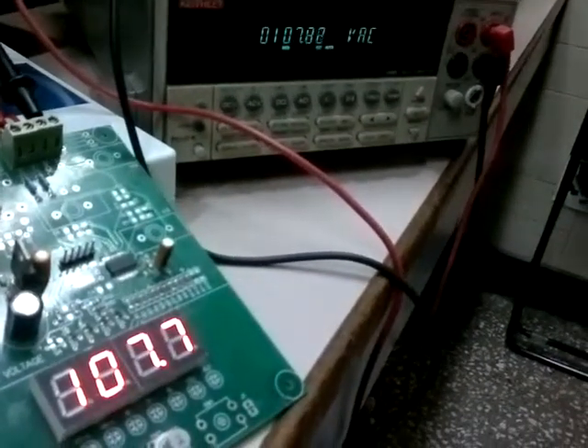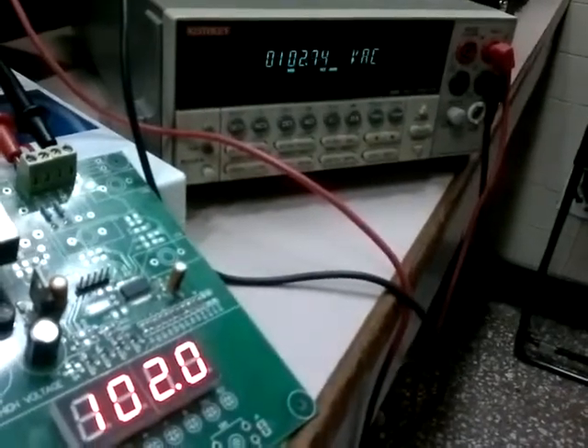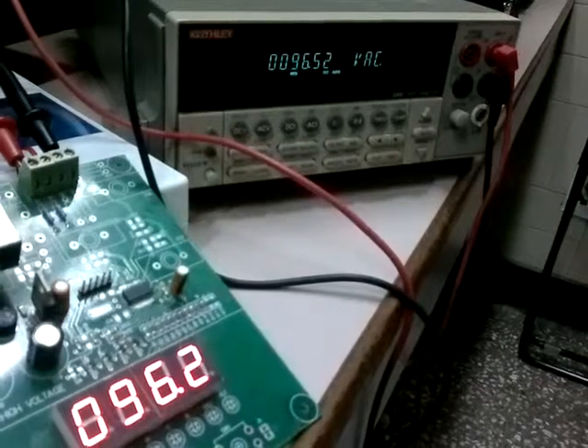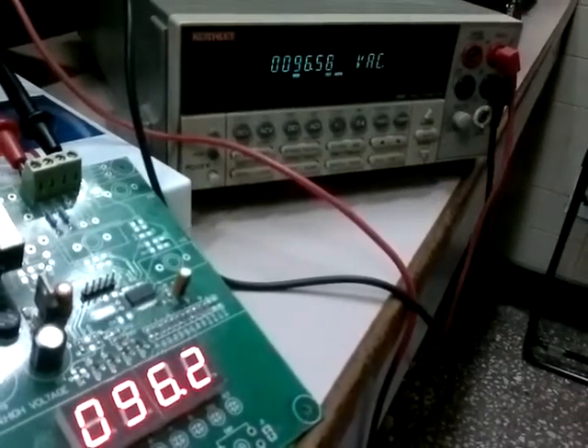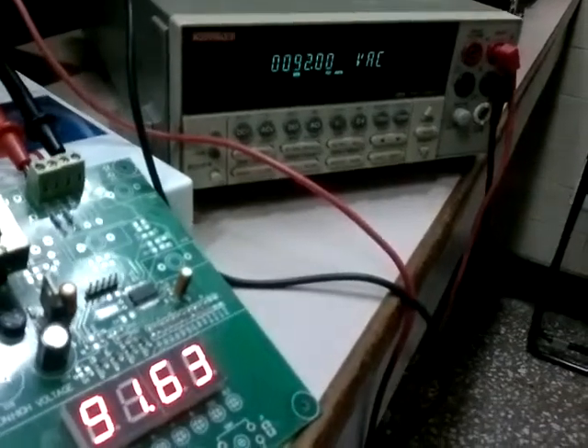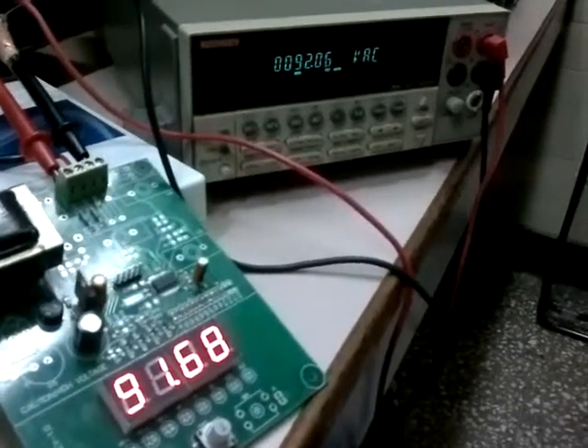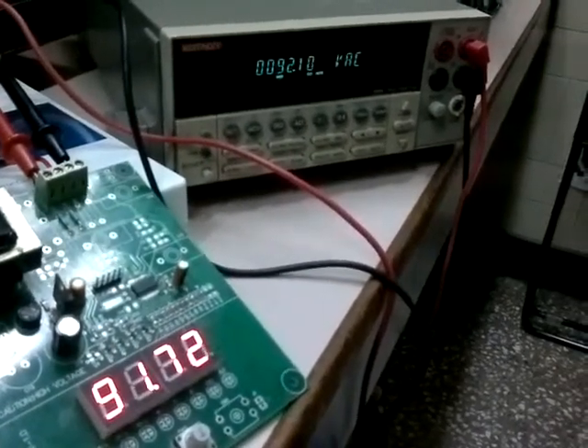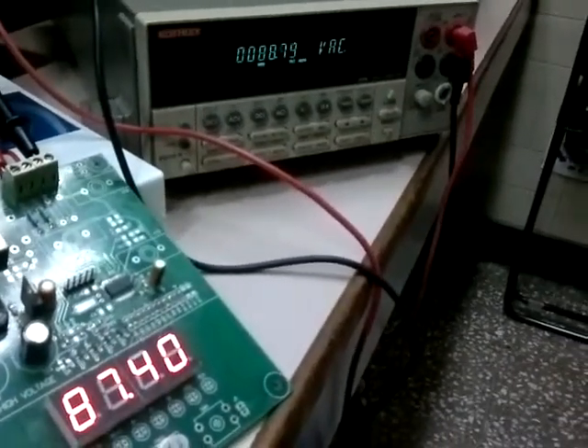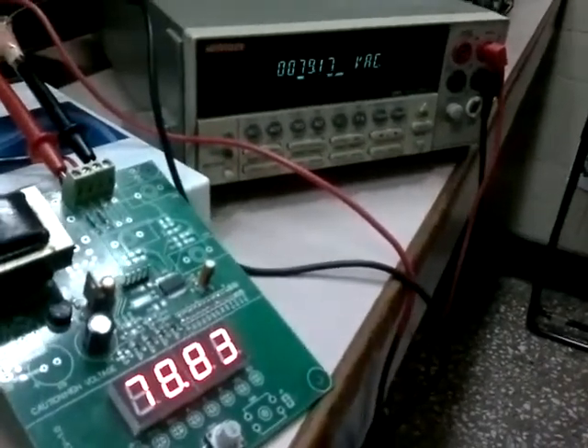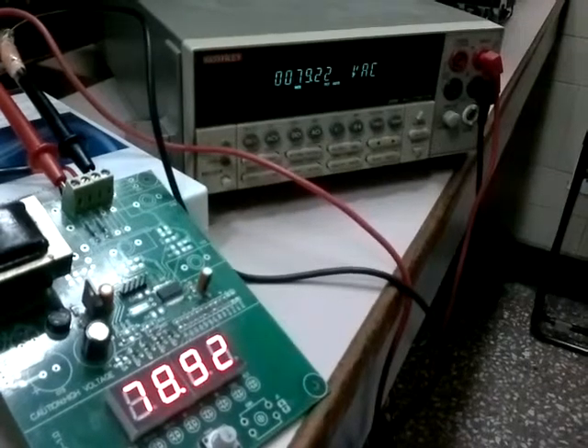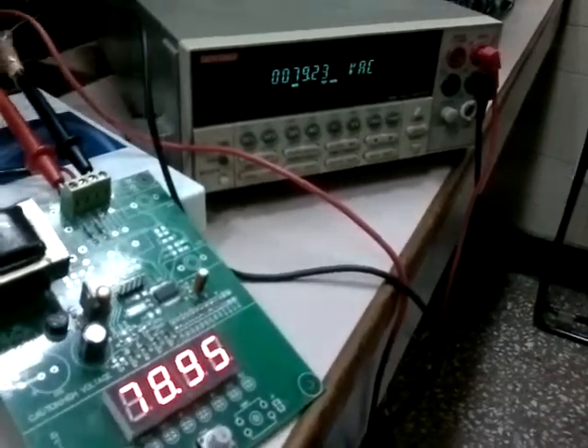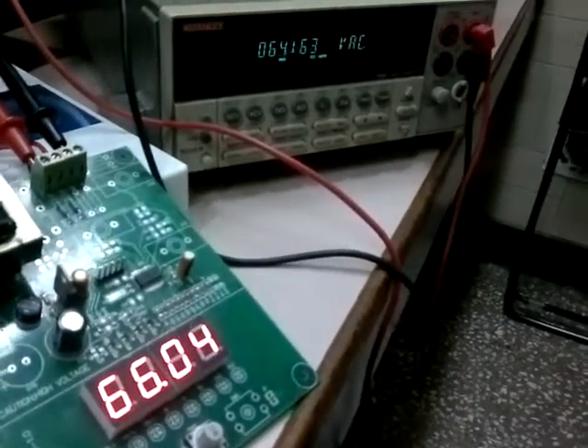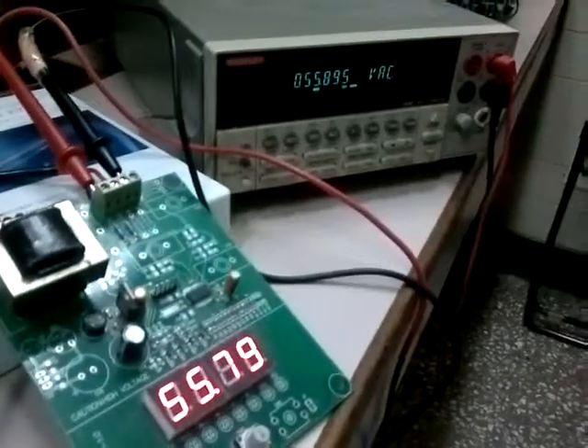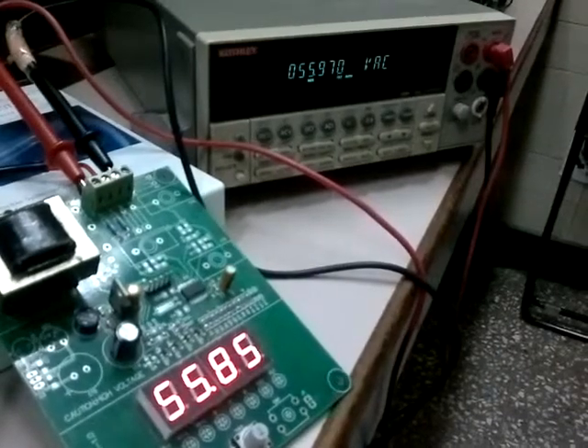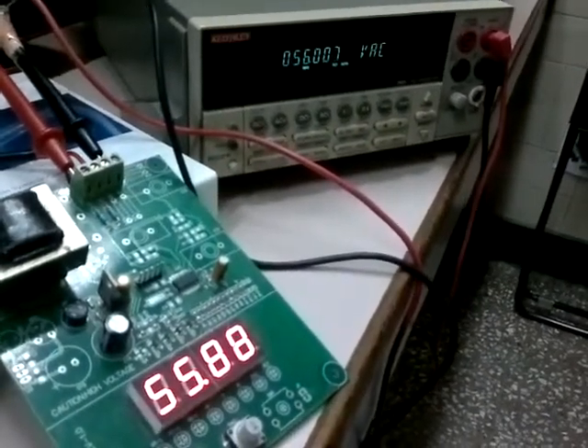And now as we go below 95-93 volts, the DPM should auto range. Now you have seen that the decimal point on the DPM has changed, so it has auto ranged itself, and we can now compare it against the meter. So we can see that we are within about 0.3-0.4 volts of the actual readout on the meter. These inaccuracies can also be because of the very average setup that we have here.